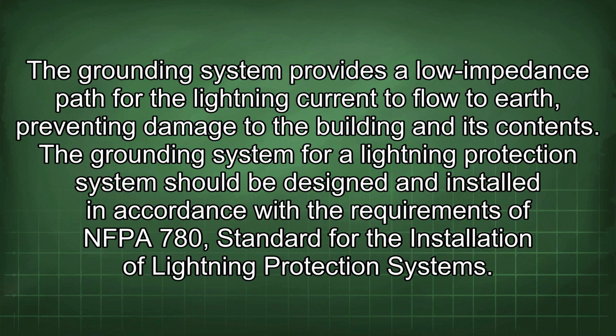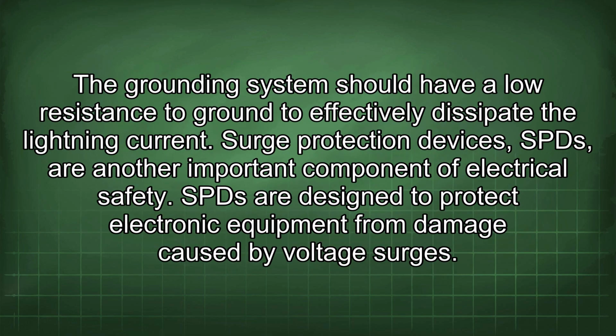The grounding system provides a low impedance path for the lightning current to flow to earth, preventing damage to the building and its contents. The grounding system for a lightning protection system should be designed and installed in accordance with the requirements of NFPA 780 standard for the installation of lightning protection systems. The grounding system should have a low resistance to ground to effectively dissipate the lightning current.